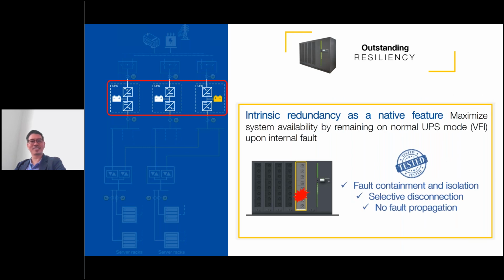When it comes to resiliency, this kind of technology has been in the market - what we call brick technology, or modular. However, not all bricks are made the same - some bricks are not resilient. So one of the integral things we have put into the system is how we can make it more reliable, making sure that the fault does not propagate to the next module. We have fault containment and isolation to make sure it disconnects from the rest of the system, so the system will be able to continue to operate even though one brick has failed.